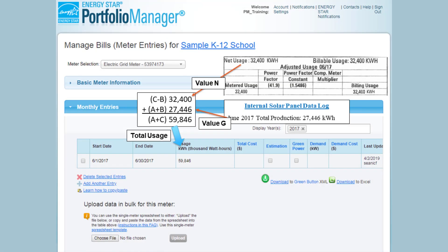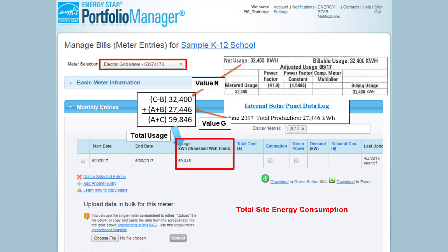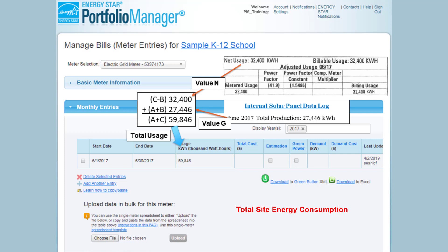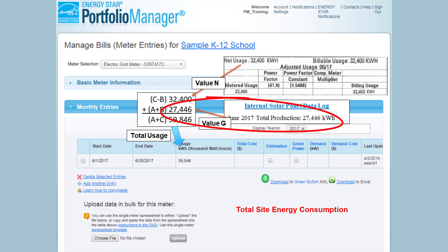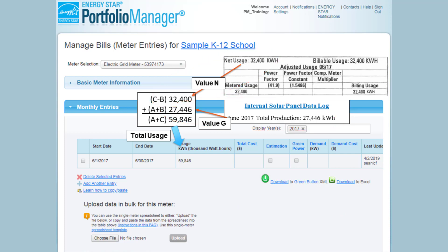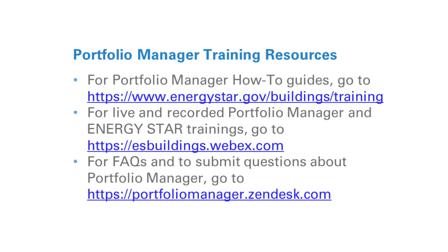As noted, we will enter total site energy consumption into the usage field of the electric grid meter. To calculate total site energy consumption, we must add the net metered consumption from our utility bill, N, to the total on-site generation from the same billing period, G. In this scenario, we would not need to have a separate on-site solar meter defined, since we do not have the information necessary to populate it with the data that Portfolio Manager requires. Thank you for watching this demonstration. For more information about Portfolio Manager, including how-to guides and videos, live and recorded webinars, and frequently asked questions, please visit the websites listed here.